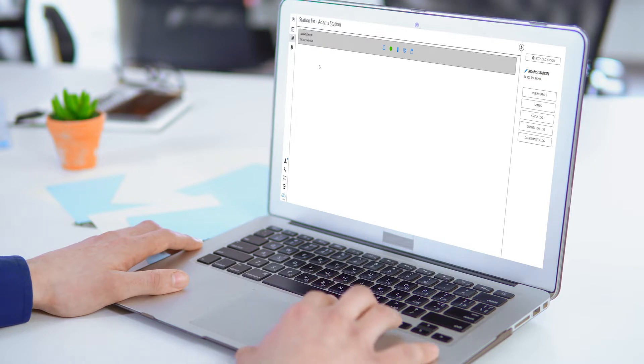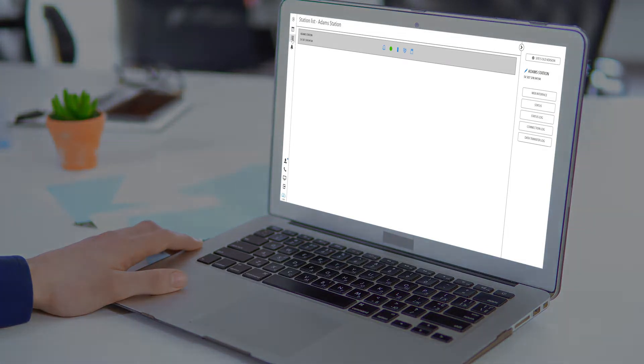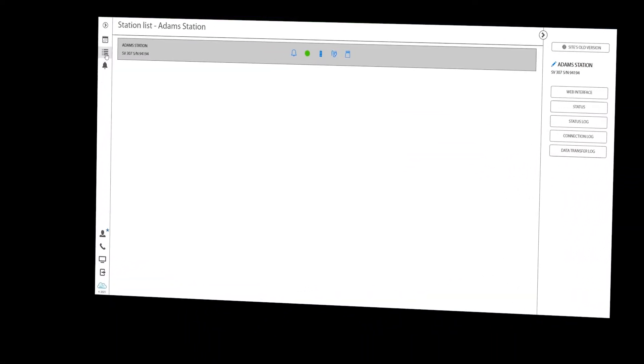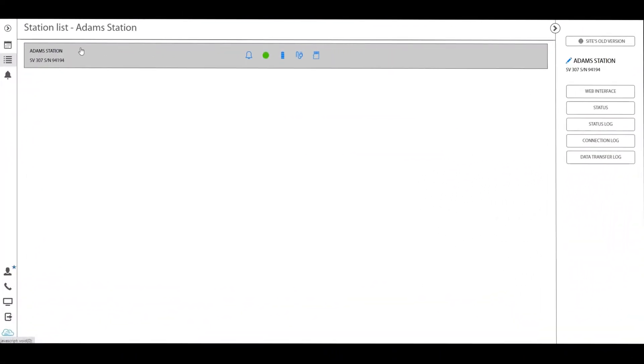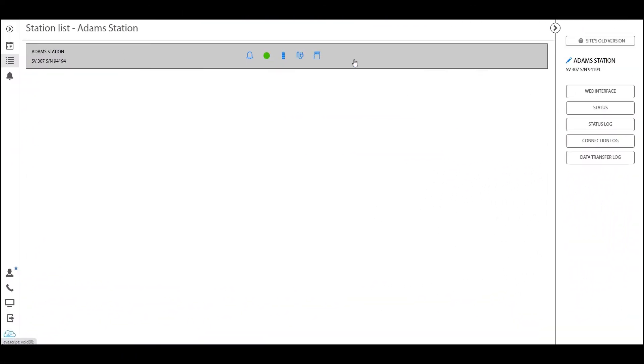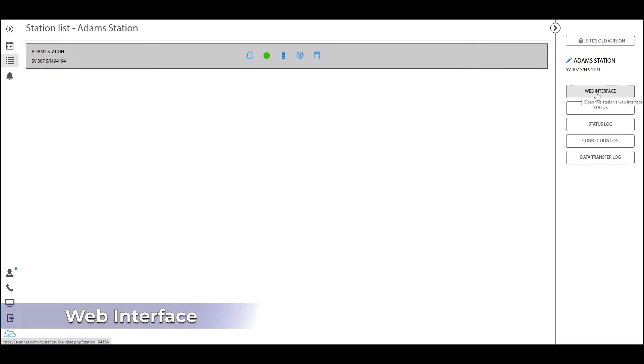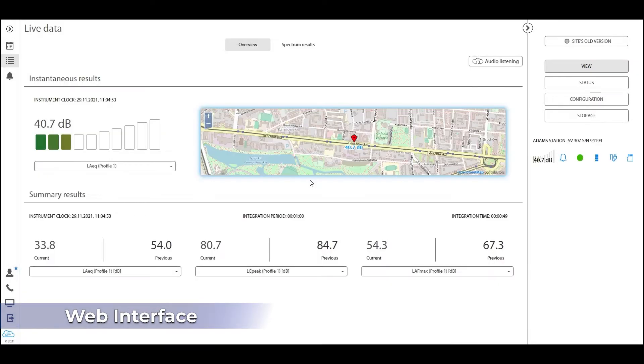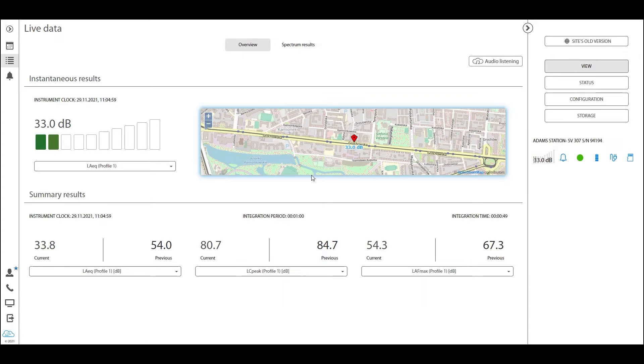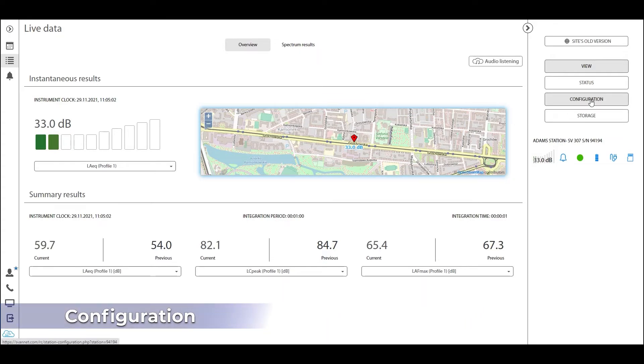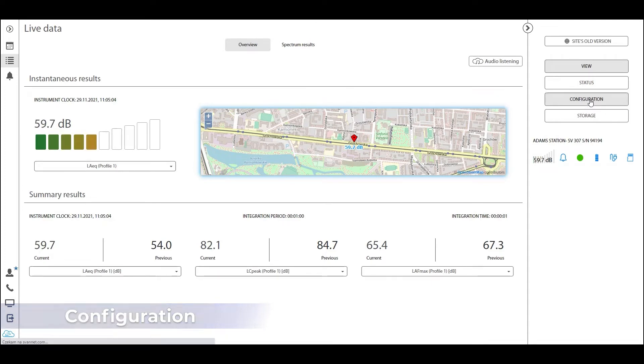Changing station parameters is done through the station list. You must go to station list, find your station, and proceed to the button in this right panel called web interface. Click that. This takes us to the live data view, which we have gone through in a separate video. But in order to start configuring the settings of your station, you must go to the configuration button here in the right-hand panel and click on that.